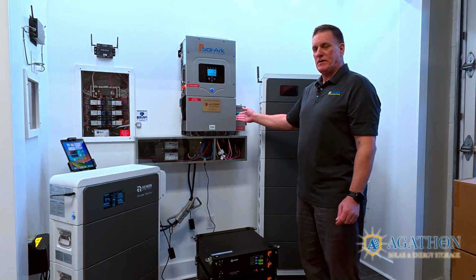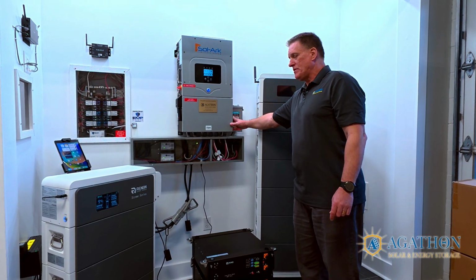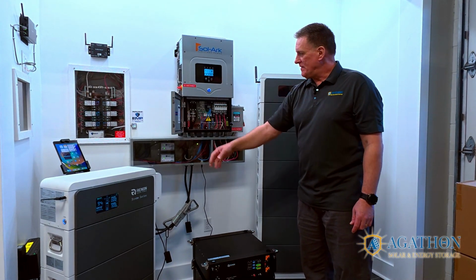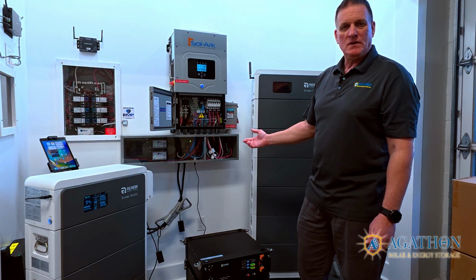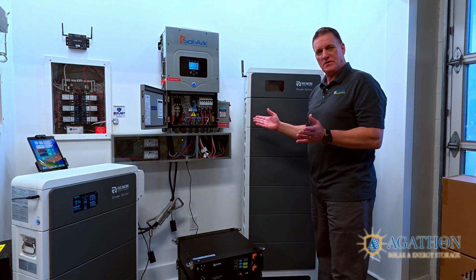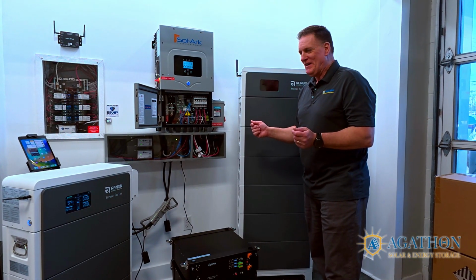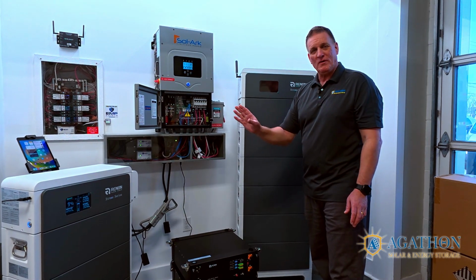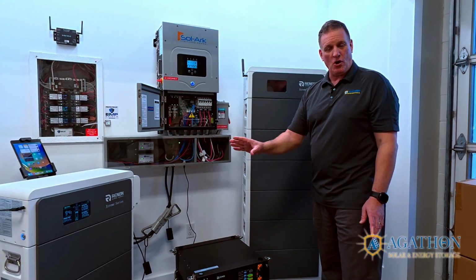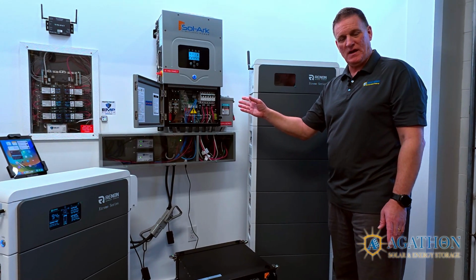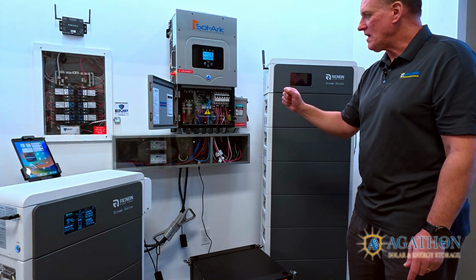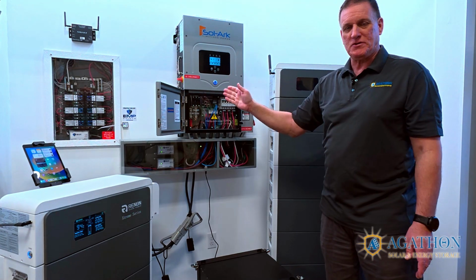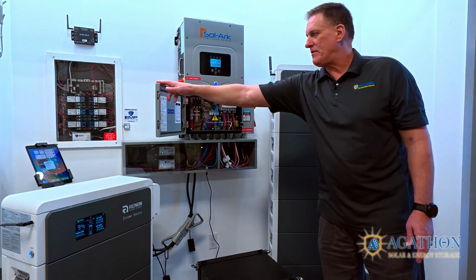There's also a generator integrated into this Sol-Ark inverter, which is a 12K inverter. In the event that there was a prolonged outage and there was no sun, which is common here in Michigan, and that battery was depleted or it reached its state of charge that was preset, depth of discharge, this inverter would tell that generator to start. It would power these loads and charge that battery.